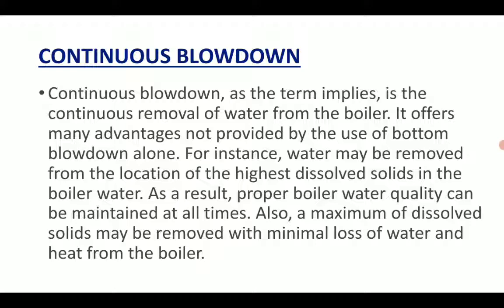Continuous blowdown, as the term implies, is the continuous removal of water from the boiler. It offers many advantages not provided by the use of bottom blowdown alone. For instance, water may be removed from the location of highest dissolved solids in the boiler water. As a result, the proper boiler water quality can be maintained at all times. Also, a maximum of dissolved solids may be removed with minimum loss of water and heat from the boiler.